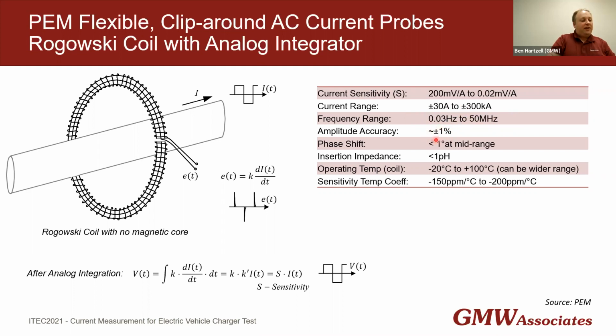An amplitude accuracy of about 1%, and the position of the primary conductor within the cable only has a slight effect on the amplitude accuracy. It doesn't have to be centered, just generally farthest away from the join, but otherwise the position doesn't particularly matter. Phase shift 1 degree at the mid-range of the frequency response, very low insertion impedance, a wide operating temperature, and not here in the specs is the wide range of physical sizes. You saw the small one. This is a mini coil, which the mini ones can be as small as 80 millimeters and 1.7 cross section, but you can have coils all the way up to several meters long.